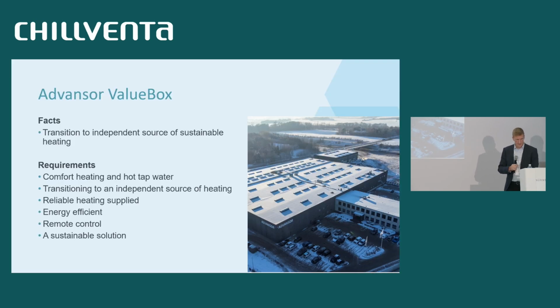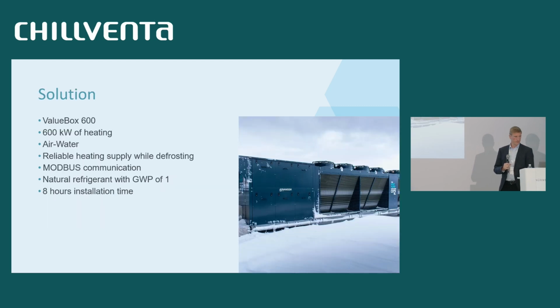Then I just have a case here that I want to show you. This is our own factory in Denmark. Here we wanted, of course, to take our own medicine and test our unit. So we decided to install a heat pump providing the comfort heating and the hot tap water for the building. Here's how it looks. This is the biggest unit we have. We call it ValueBox 600. It produces 600 kilowatts of heating. It's air to water, and it's been integrated into our building management system.